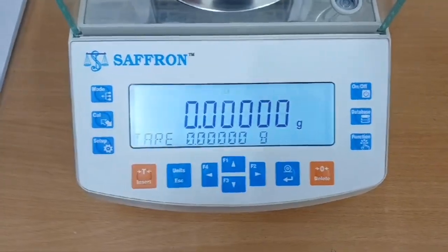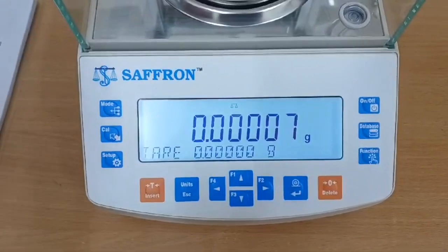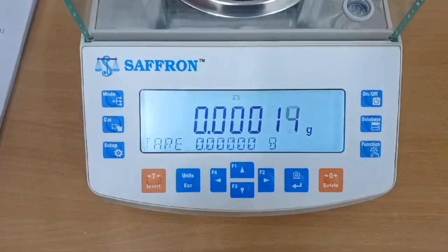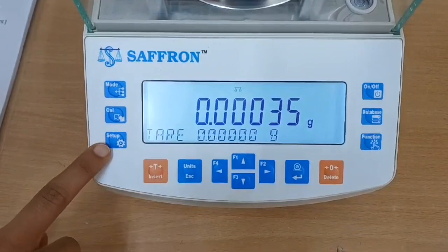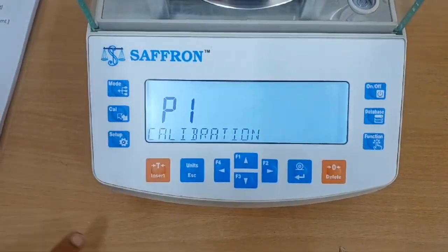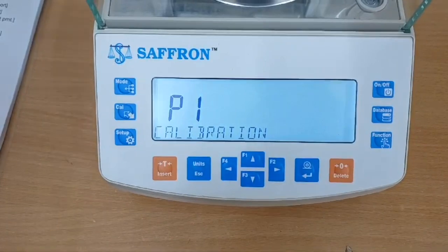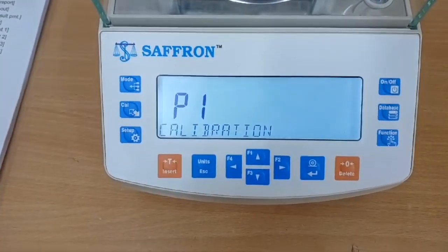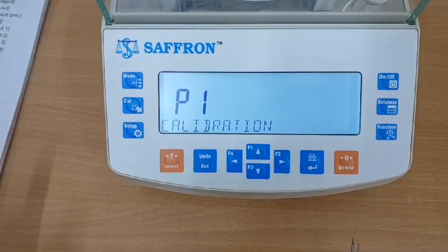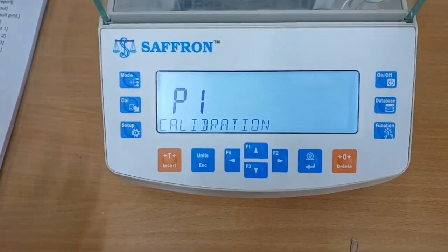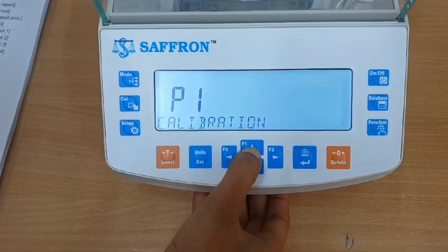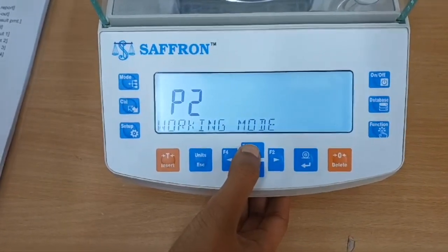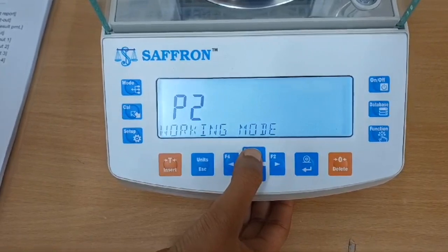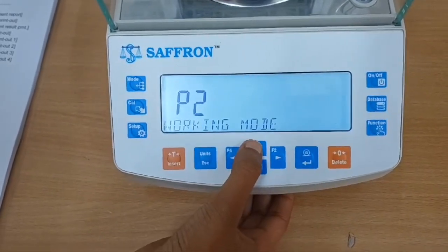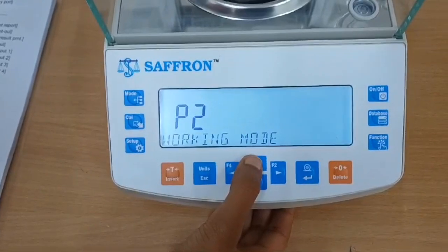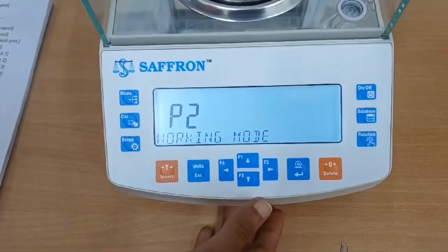Now we'll show you the different settings that can be changed. In order to change these settings, you need to be logged in as admin, but we'll just show you where it's available. So first we go to setup. As you can see, the first one is calibration or adjustment. Here you can access the internal calibration, external calibration, user calibration, etc. We then have the working mode or operation mode. This provides access to the accessibility, the weighing, the counting pieces, the check weighing, dosing, etc. This is not required for the general use.